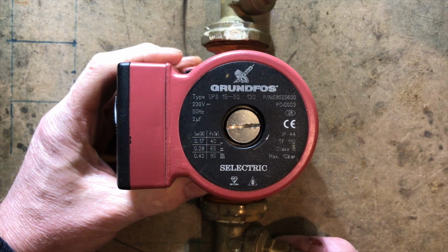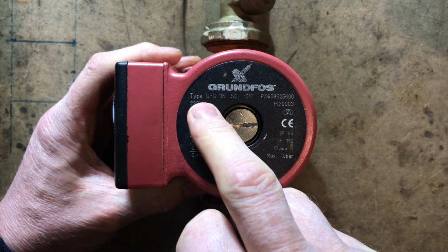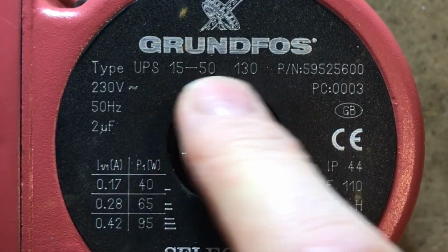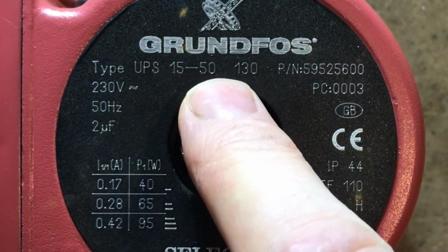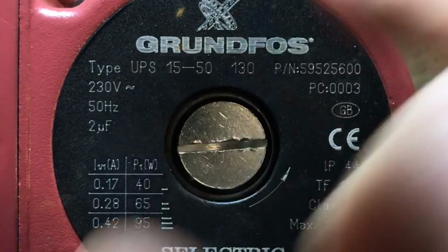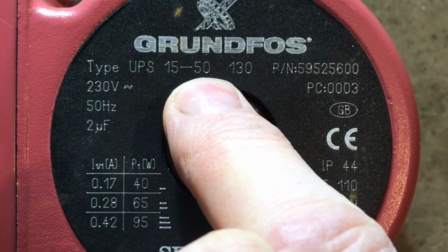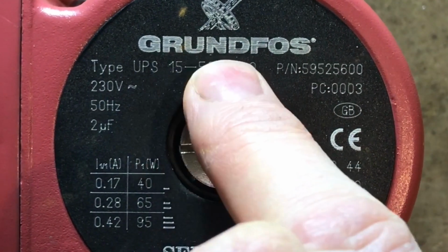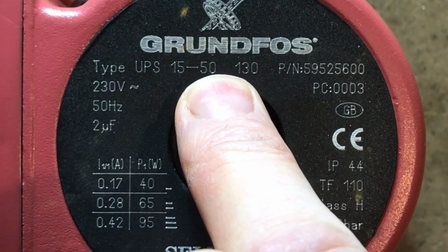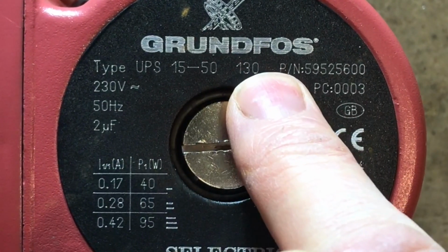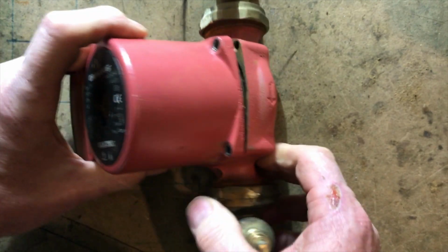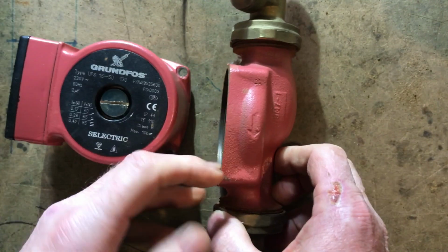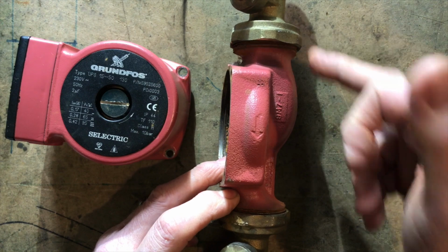Now, last couple of things with the head. What we've got here, we've got some numbers here. So 1550 means 15 is the diameter inside here, and the 50 means 5 meters head. So if it was a 1560, it would mean it was a 6 meter head. And the 130 there means from face to face of these flanges, it would be 130 mil.